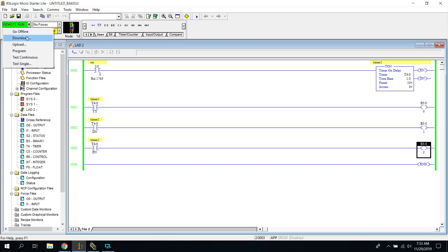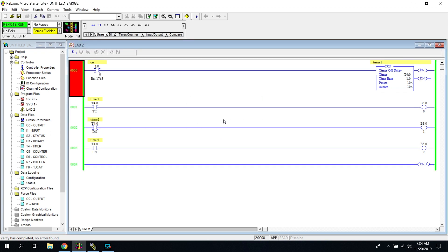Let's go offline and change this to a timer off delay, then download again. Now when I press the blue button, notice the timer done is already on and the timer is not timing — it's just sitting here waiting. As soon as I release this button and it becomes false, the timer now starts and the timer timing is running. As soon as it hits 10, all of this is going to turn off. Pretty interesting — a lot more confusing than using our timer on delay.